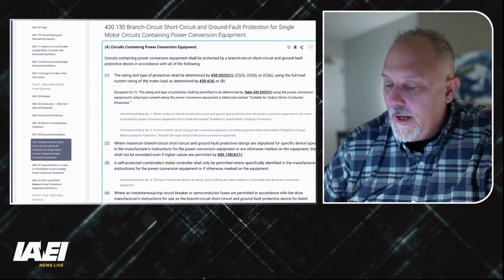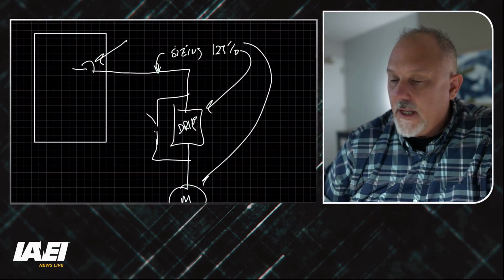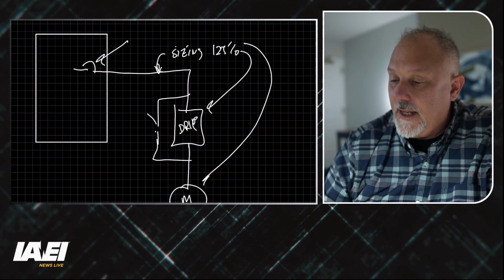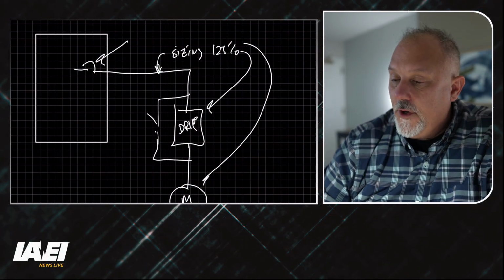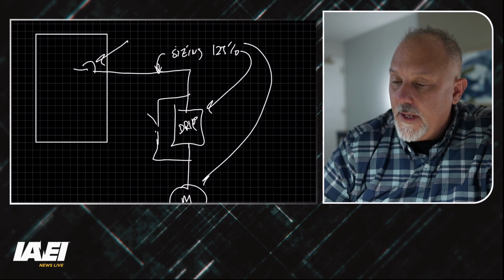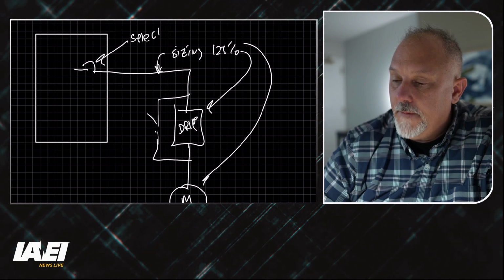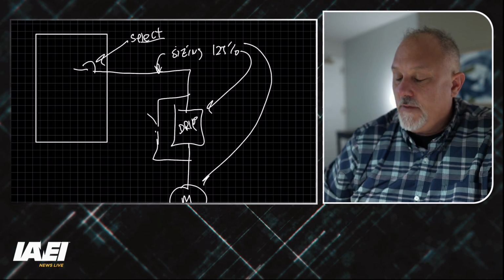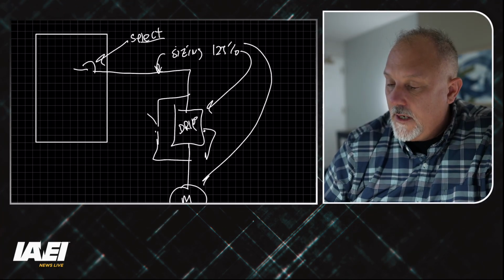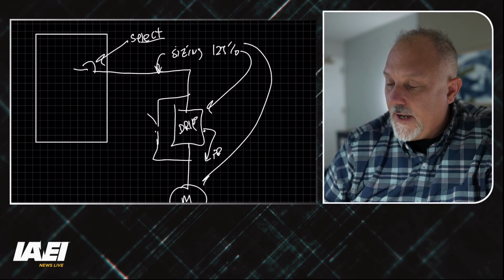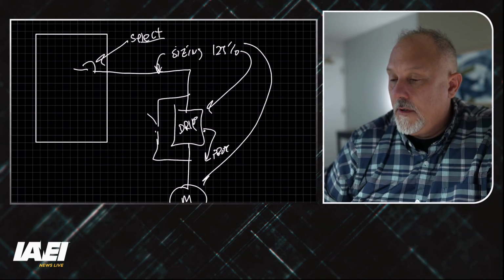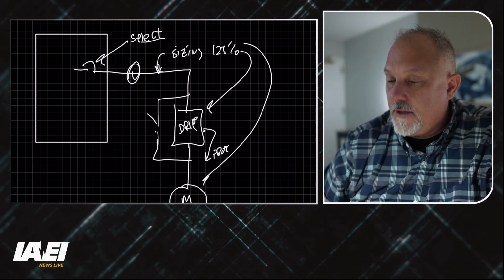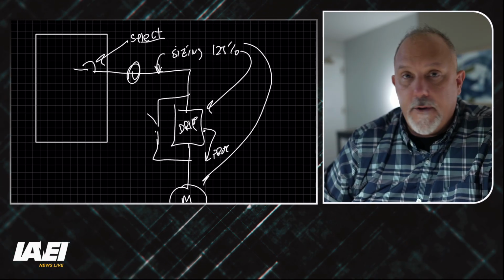I mean, why wouldn't they make it just as neat and clear to say, look, you have a drive, you have to select that overcurrent device, and then this has to provide protection downstream. I've got to protect this conductor, and that's going to be protected by the primary overcurrent device.